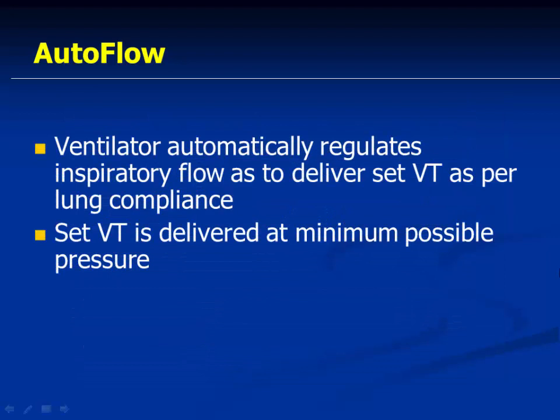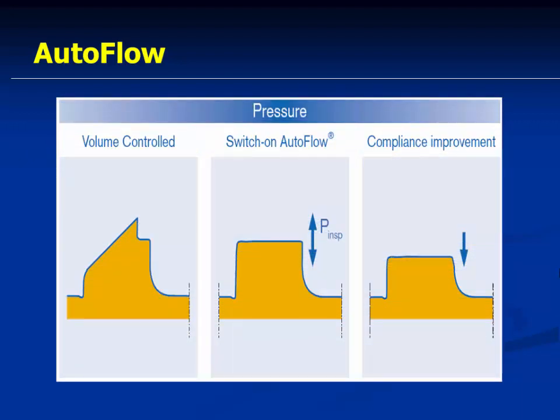The ventilator automatically regulates the inspiratory flow so as to deliver the set tidal volume per lung compliance. The set tidal volume is delivered at the minimal possible pressure. So the ventilator is changing flow to deliver at minimal possible pressure. This is what is happening. These are pressure waveforms, volume controlled.